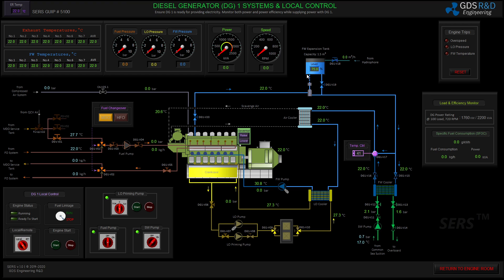The expansion tank level is 75% right now, which is good. I will open the inlet and outlet valves of the fresh water cooling system. I won't be able to start the fresh water pump because it is an attached pump — it will start as the engine starts turning.